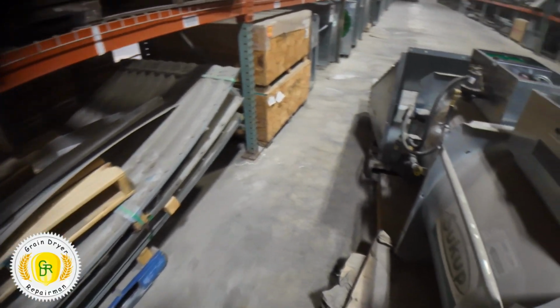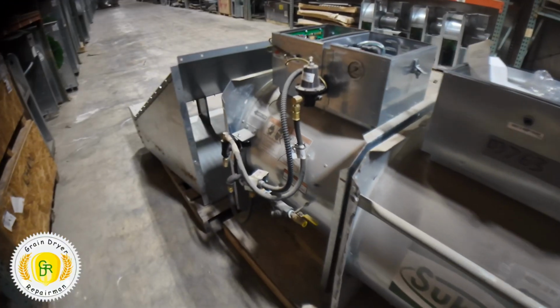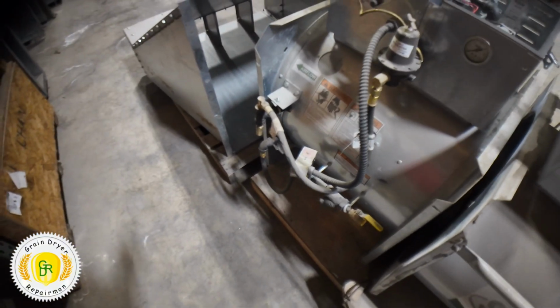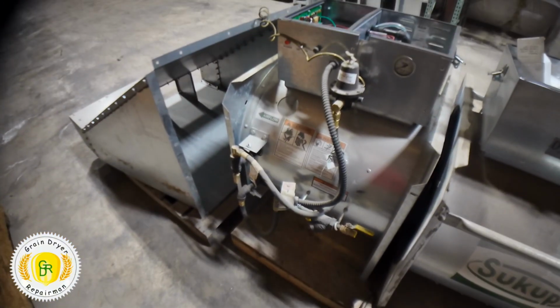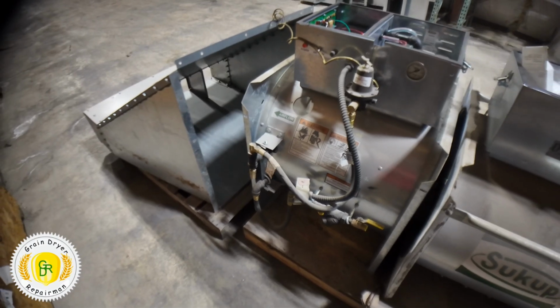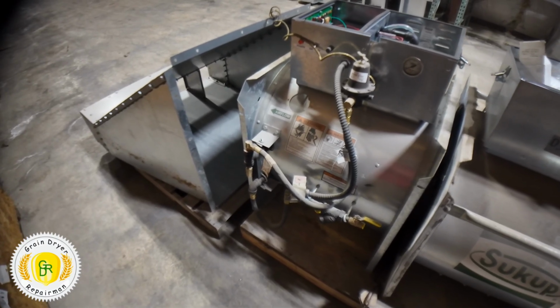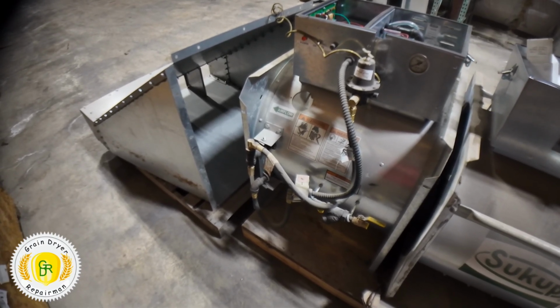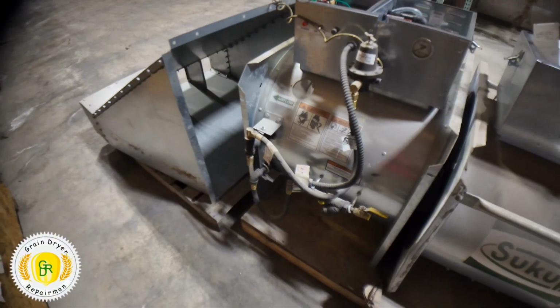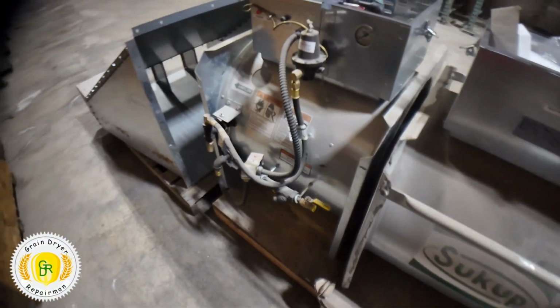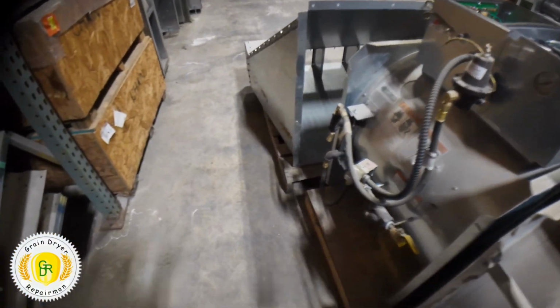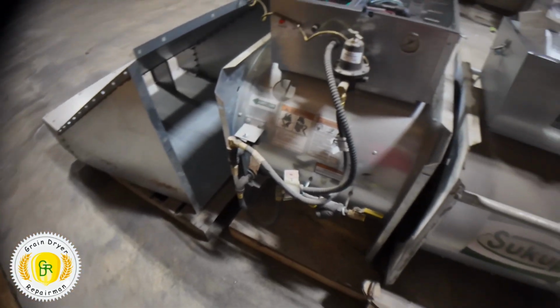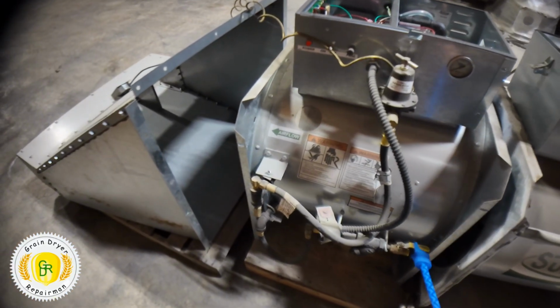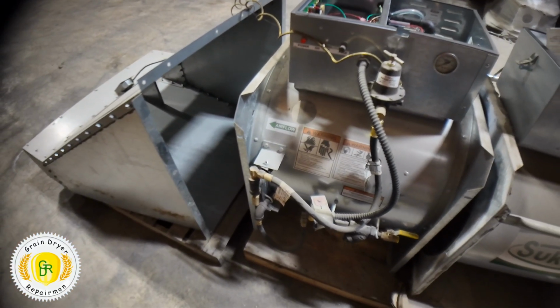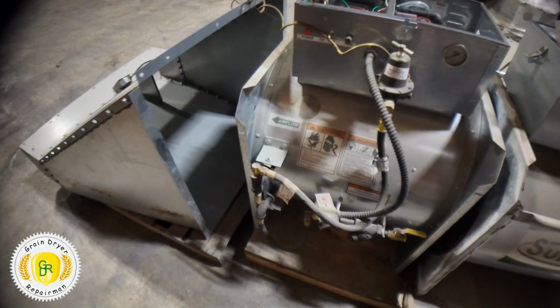If you are connecting natural gas, you're going to need 12 pounds of natural gas, 10 pounds minimum. It's rated at 12 pounds of natural gas. If you are connecting propane, you need to connect tank pressure to the burner. The burner requires tank pressure.